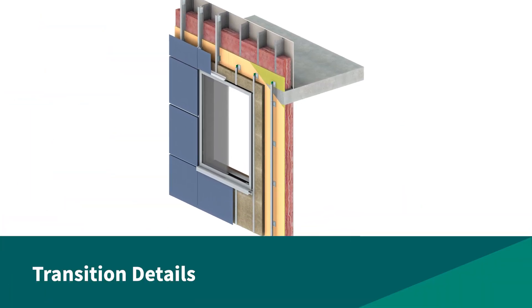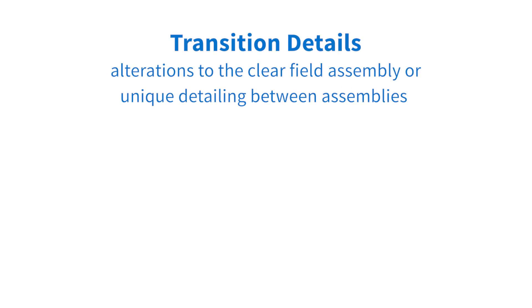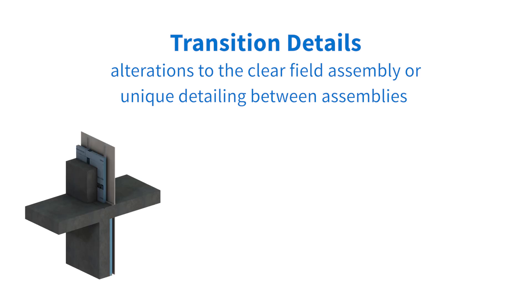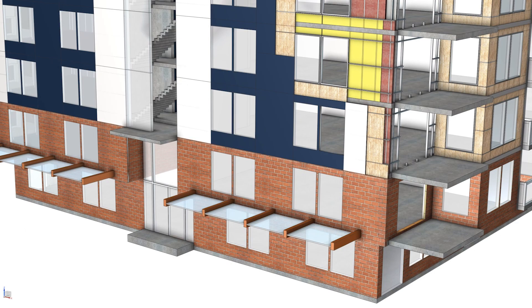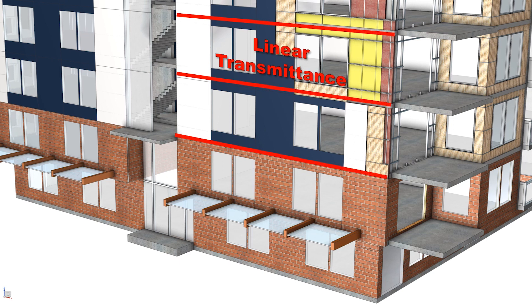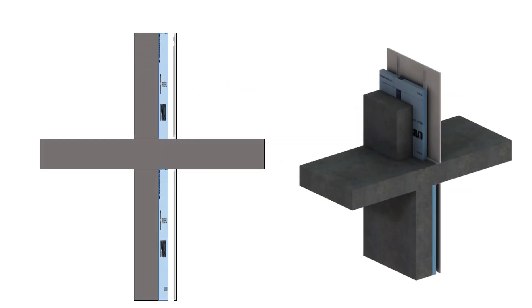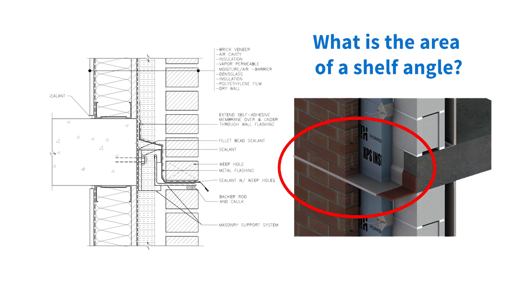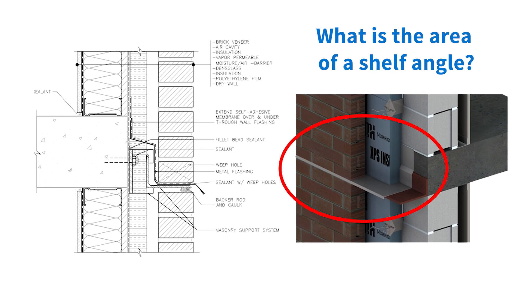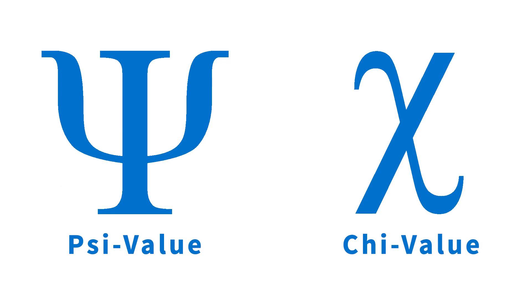Transition details often intersect or alter the clear field assemblies at specific locations, such as slab edges, parapets, and window transitions, which can create additional thermal bridging. Transition details can be separated into two types: details that can be defined as linear, such as slabs and parapets or other details that go across the building face, or point details that occur in single infrequent locations such as beam penetrations and pipes. While transition details may not take up a large area of the envelope, the impact they have on overall thermal performance can be significant. Most linear and point transition details are difficult to give an area-based U value to; therefore, they need a different way to calculate heat flow through these details, which is where psi and chi values come in.